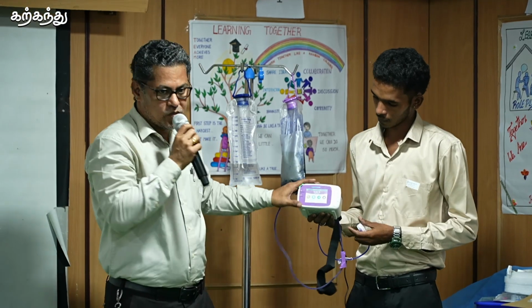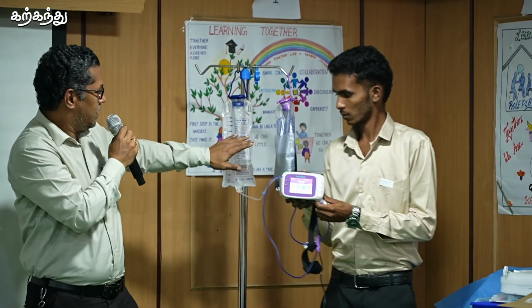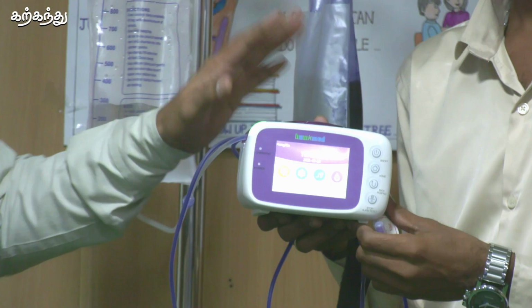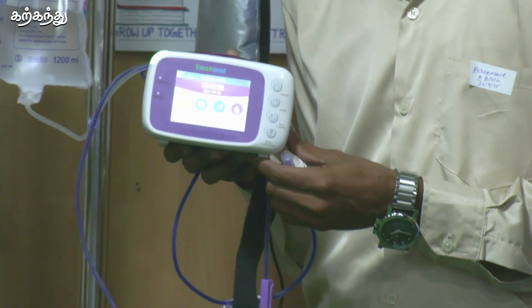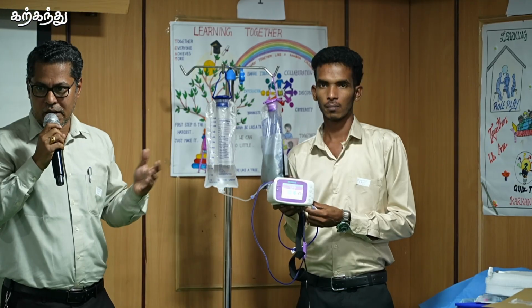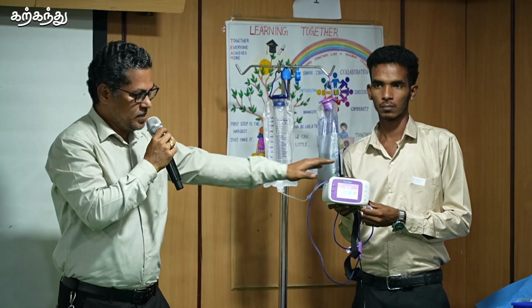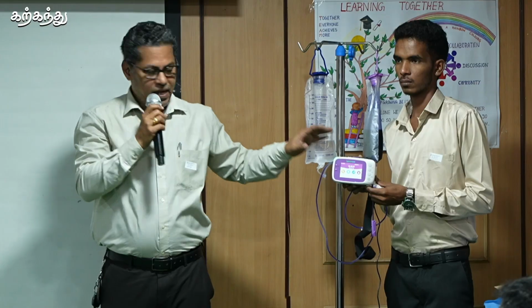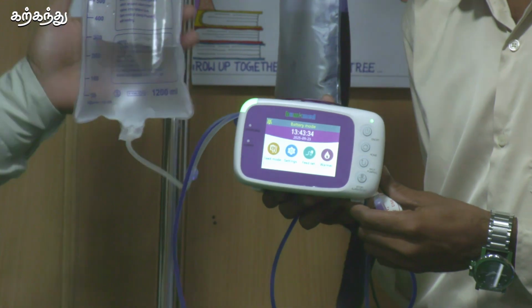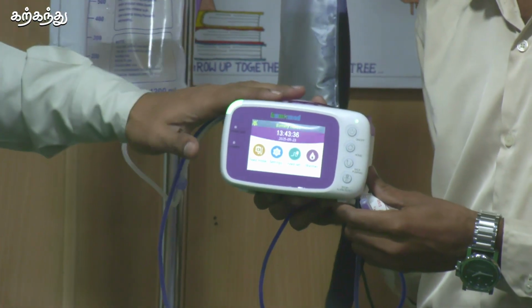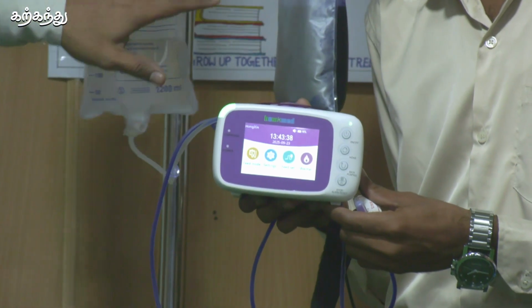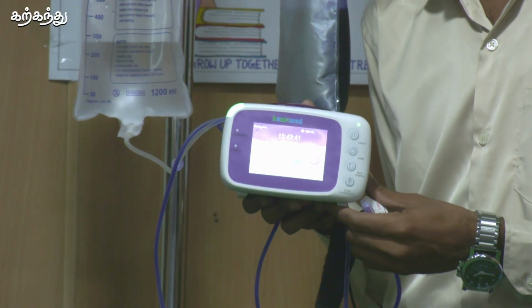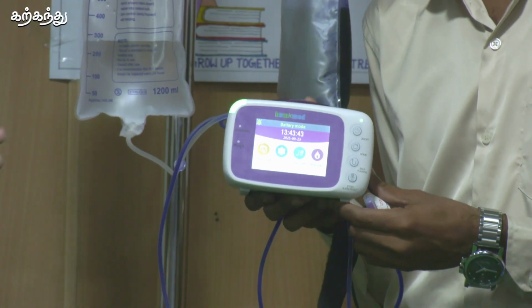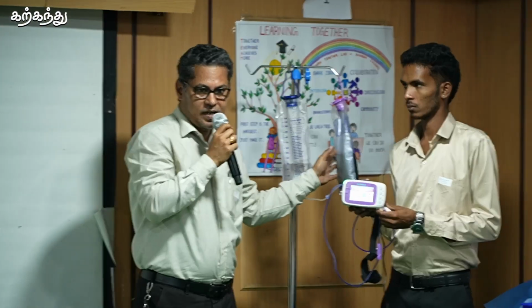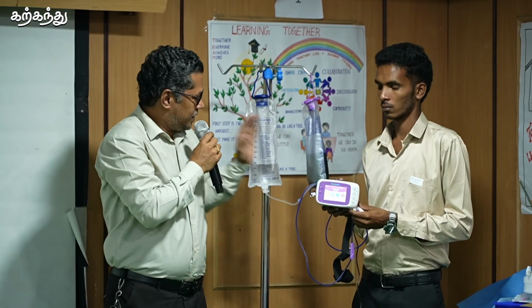The first advantage of this pump is that we need to key in whatever parameters are required, say 50 ml per hour or 100 ml per hour, to set the feed rate, followed by the flush rate. Once that is set, we can also set the intervals, whether every 15 minutes, 30 minutes, or 1 hour. The feed will start, and once the feed stops, the flush will start.